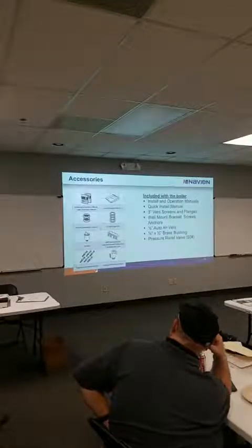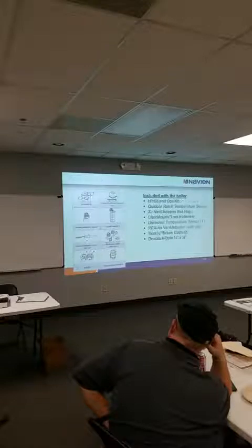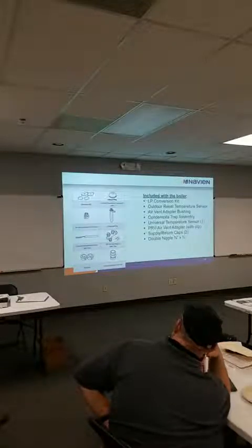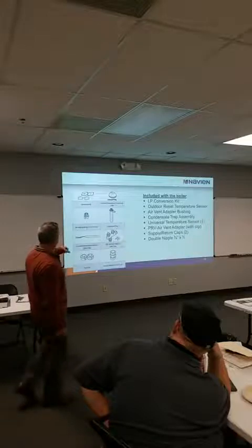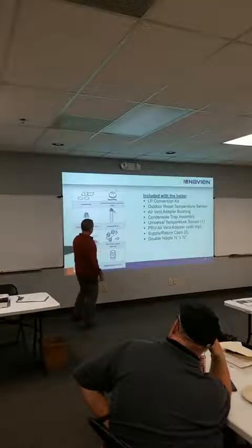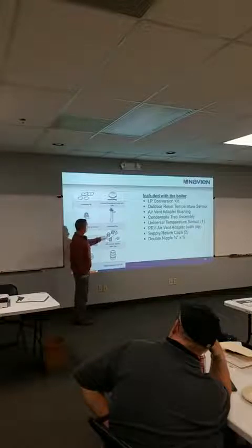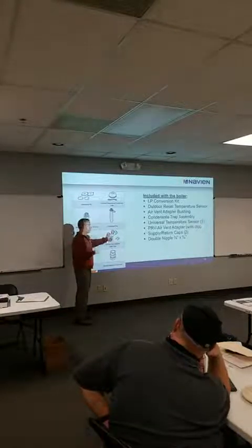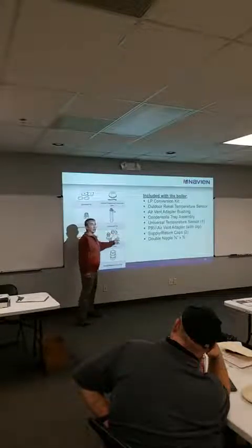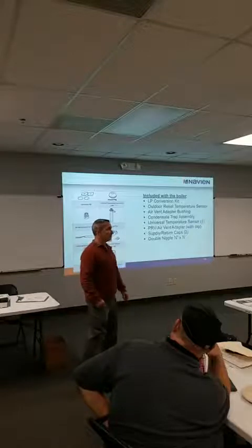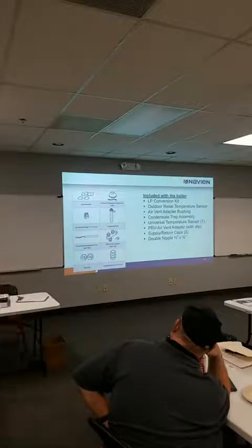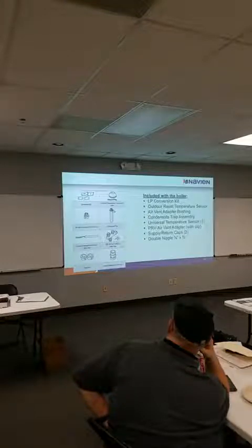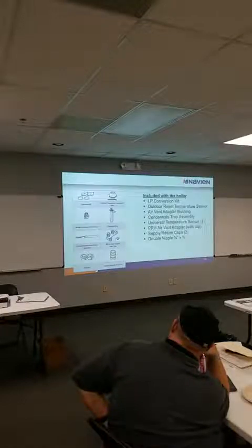So this is what comes in the box itself. So we give you an air vent, we give you a pressure relief valve. Here's your accessories. Oh, sorry, this is what's included in the box also. So here's your sensor. You get this air vent adapter which plugs into the top. So it gives you a port for a relief valve, a port for a little air eliminator, and it's also plugged on one side, where you could put an external low water cutoff if you want, and wire that back to the board. Oh, it's probably 1 inch. It's probably a good guess. The nipple says 3/4. It's that little torpedo low water cutoff, I think it's maybe 1 inch or two. And then outdoor sensor, of course.